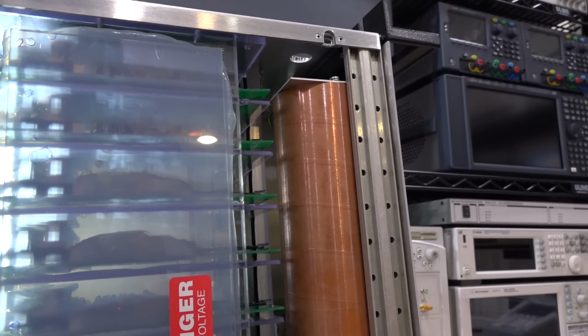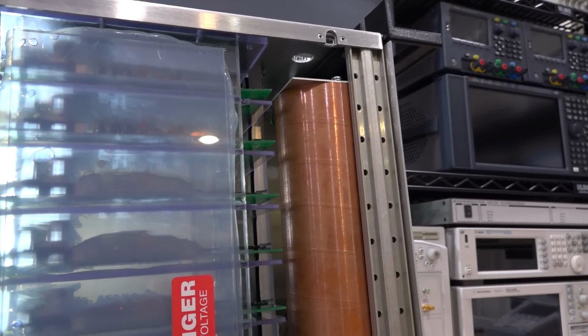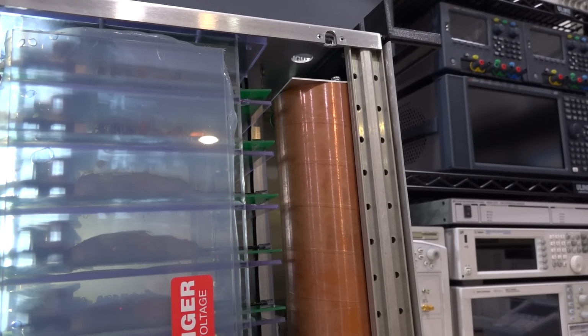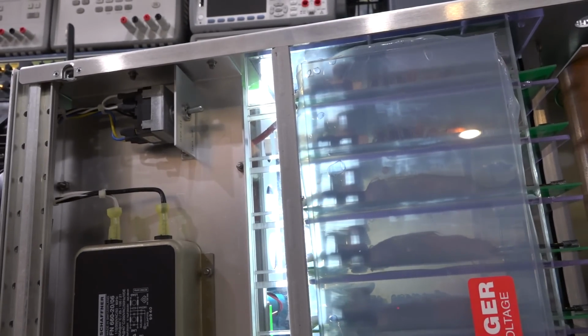But whatever they're doing there is conditioning the output, dividing it, providing the feedback in a safe way, because from here you still have to create a low voltage signal to go back, which is itself quite a bit of a challenge. And this thing does see plus or minus 20,000 volts with respect to the earth ground. Yeah, pretty complicated overall, but I can't wait to turn it on so we can play around with it.